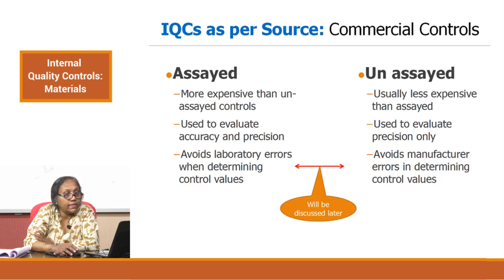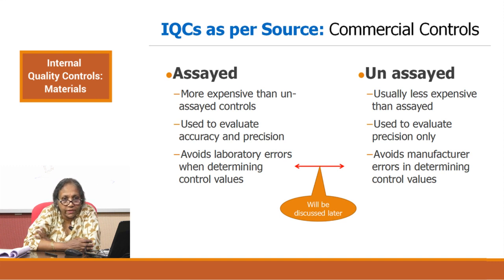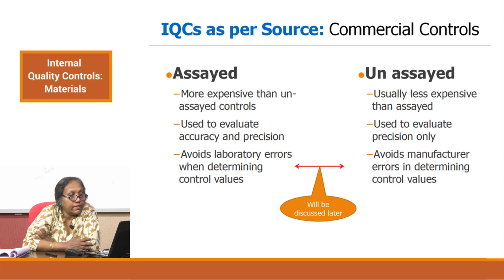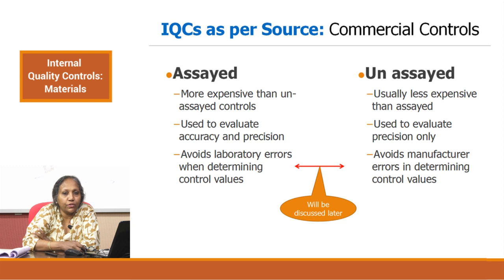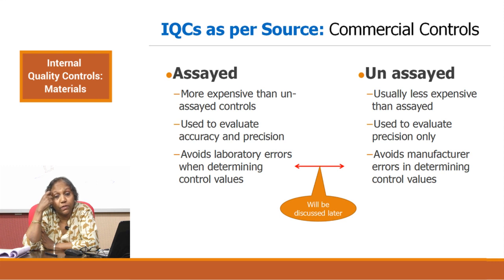Assayed controls are more expensive than unassayed controls and are used to evaluate accuracy and precision. Accuracy shifts can be determined since some idea of the mean is already provided, giving you an idea about shifts or changes in accuracy. It also avoids laboratory errors when determining control values. Unassayed controls are usually less expensive than assayed controls, are used to evaluate only precision, and avoid manufacturer errors in determining control values.